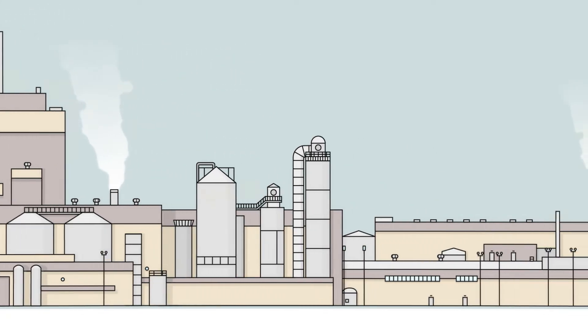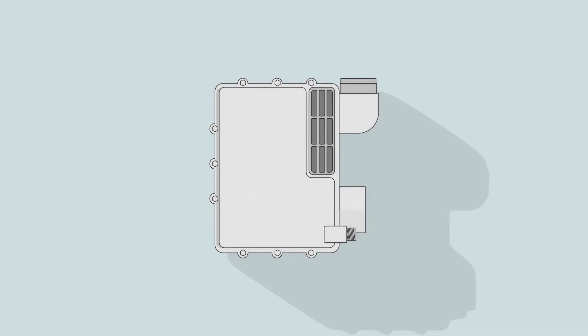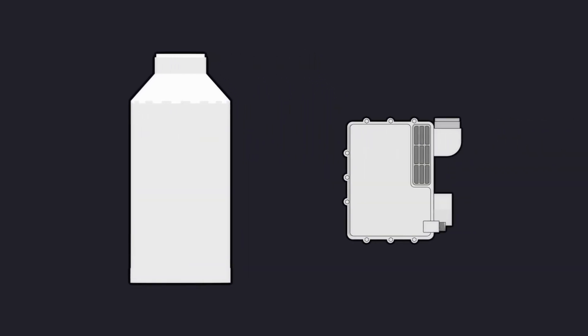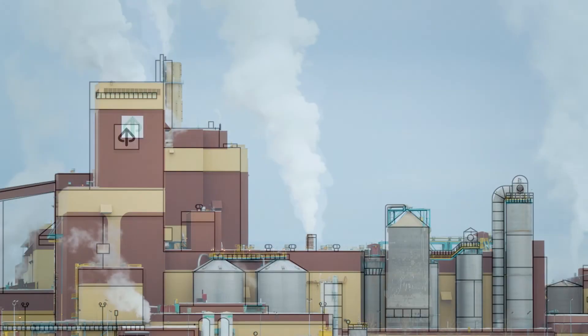Nobody's done it before — I think that's what makes it really interesting. The fact that no one's done it, and pulp mills have been around for hundreds of years. The challenge in the middle of all this is where to put that condensing exchanger. That part needs to go next to and be exposed to the recovery boiler, but the recovery boiler is a highly corrosive environment. So Elpac has embarked on testing to figure out which custom metallurgical materials will be able to withstand those harsh environments for 20 or even 30 years.